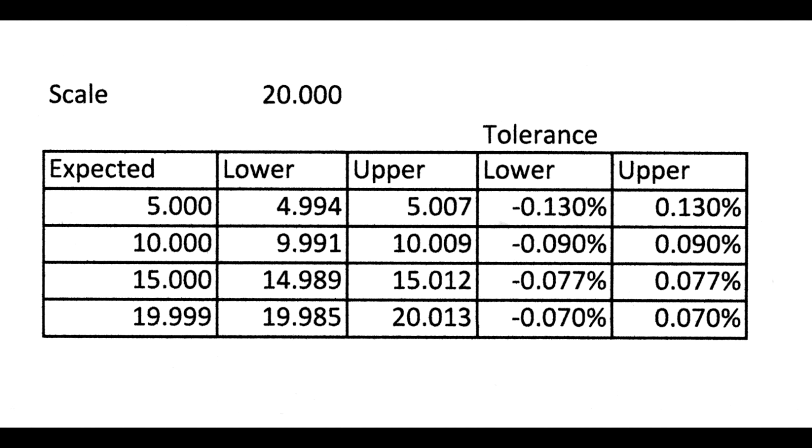At the low end of a range, the 0.02% of full scale contributes a significant inaccuracy. The nominal 0.07% accuracy is theoretically achievable only at the top of the range. However, working instruments display a much better accuracy at low voltage than the chart shows. This is probably due to good linearity in the A to D converter.